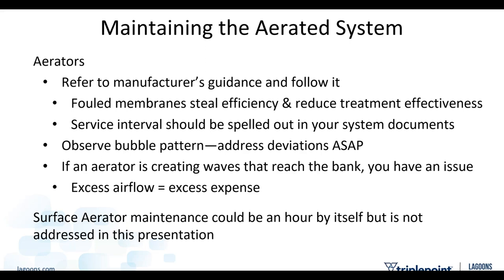And I'll just tell you that in our documents, we ask municipal systems every 5 to 7 years, pull up the aerator, spray it off, do a condition inspection. If everything's fine, put it back. The reality is that almost no one ever does this. But those service intervals on all of the pieces of equipment in your system, it's important to know what they are and try to follow them to the best of your ability.